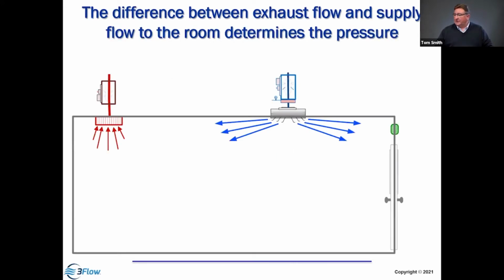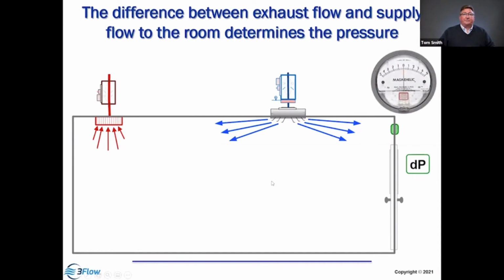Now, we also have the circumstance where we're looking at this pressurization. So we've got an airflow direction on there, but we may not have the right magnitude of the pressurization. So we want to look at what the pressurization for the space is. So for our supply diffuser and our exhaust, we take a look at this value, and if we have some type of pressure gauge. And pressurization is important, right?